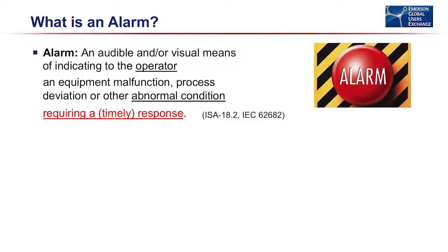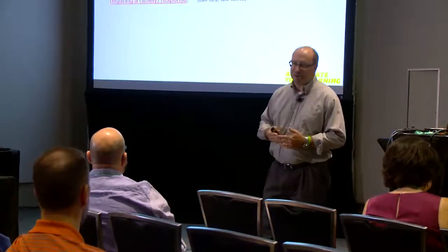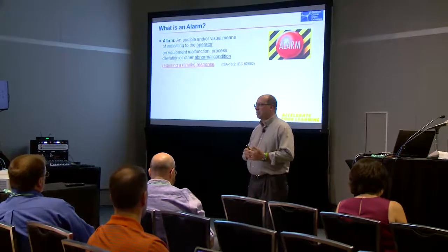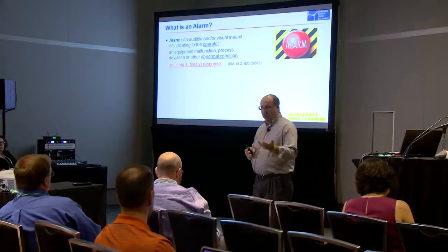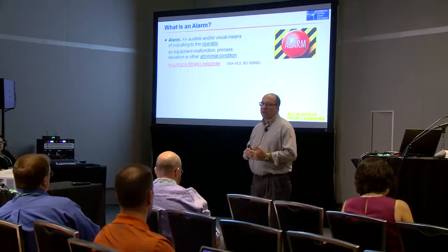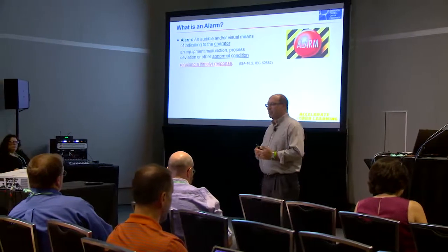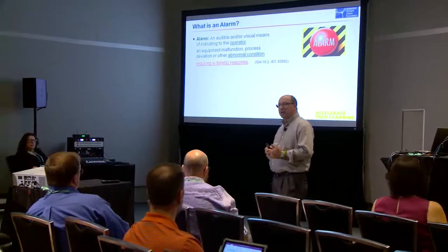Something is wrong. If we think about our sump pump example, that high-level alarm, is that consistent with the definition? Was that an abnormal condition? No, it wasn't. That was an alarm that essentially indicated it was time for the pump to turn on. Timely response. The operator must take a corrective action, something that will correct the process, something that will correct the abnormal situation. So opening a valve, turning on a pump, something like that.